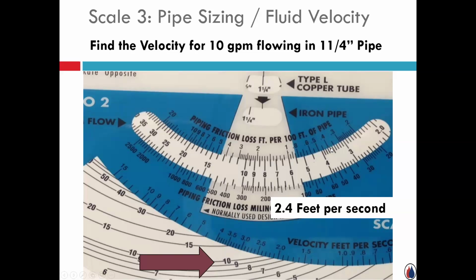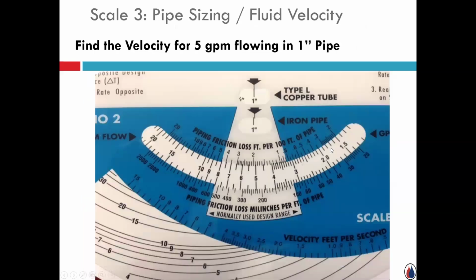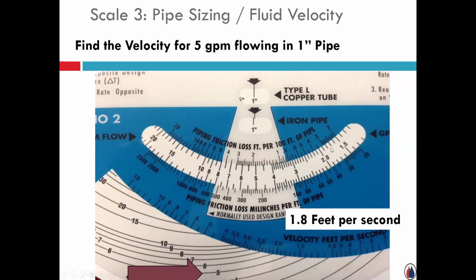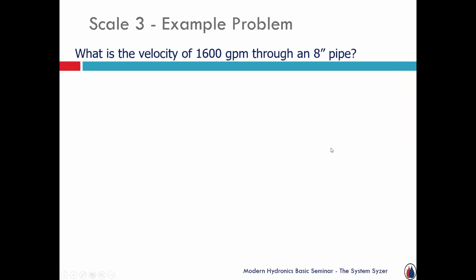Good selection. Just a confirmation. You figured it out up above on scale 1, you find your pipe size on scale 2, you glance down at 3. Hey, am I in the ballpark? Am I not too fast, not too slow? Good. Keep moving forward. And again, 5 gallons a minute, same thing. Just glance down, see the velocity. Fine, 1.8.